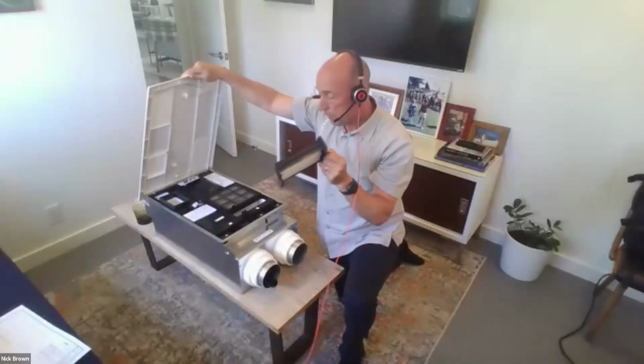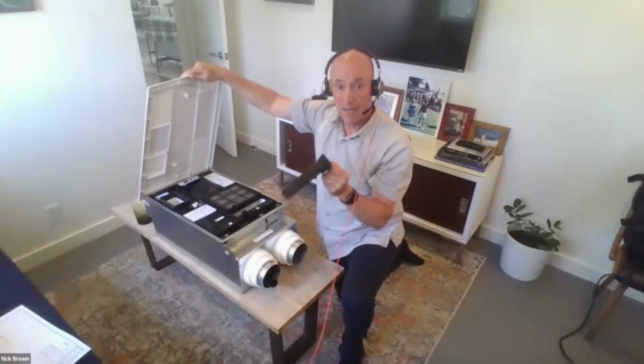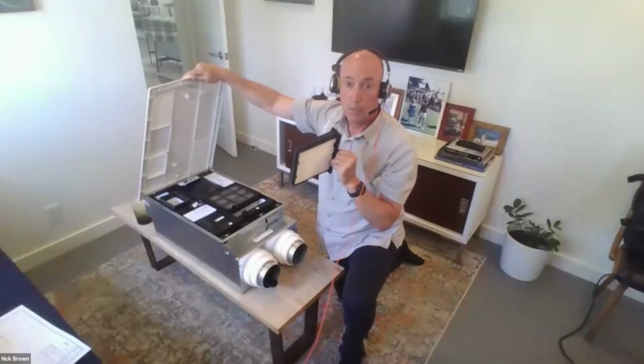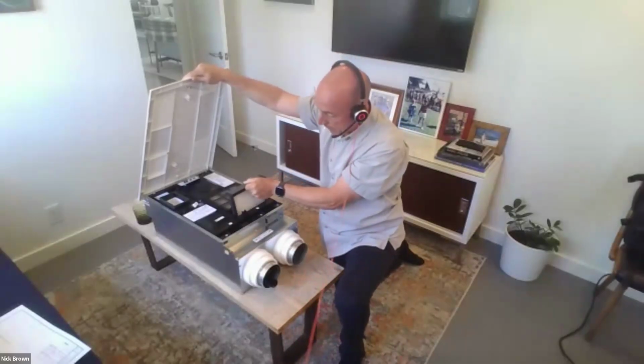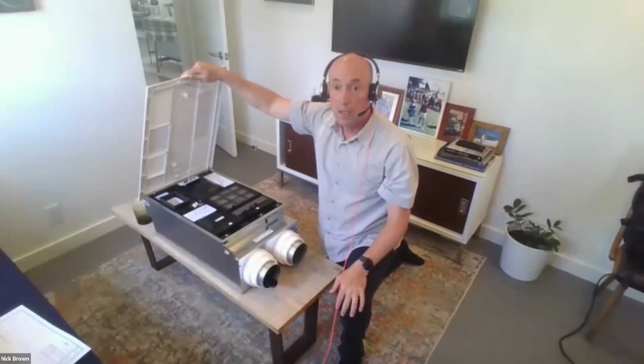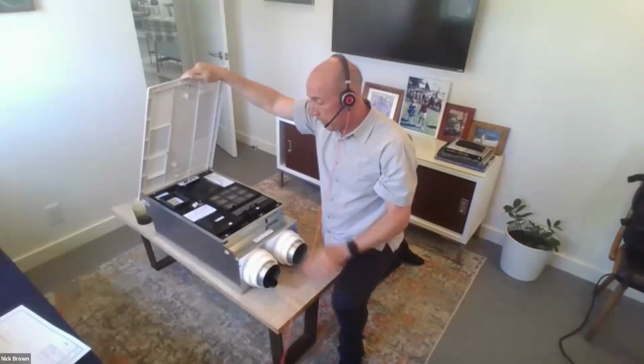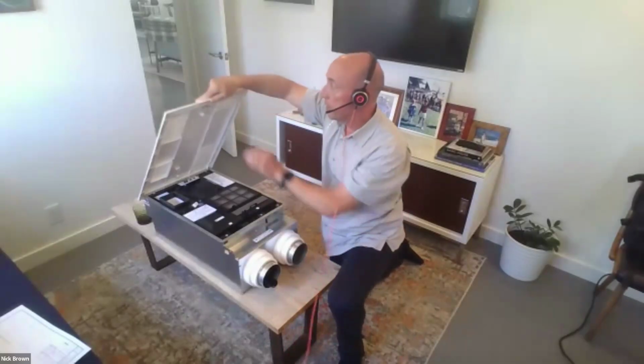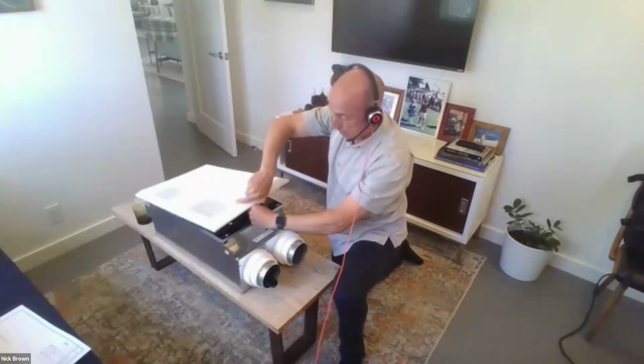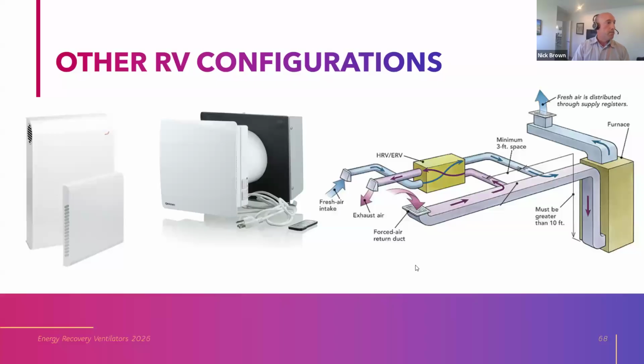I should have mentioned, in supply and balanced ventilation systems, it is mandatory to have MERV 13 filtering the supply leg of a balanced ventilation system in California. So you need to make sure you pick a system that has that capability. So I really like this adaptation because it eliminates the cost of ducting the supply and exhaust air around a small dwelling unit in a way that might allow for ERVs to be installed in multifamily buildings and small units more cost effectively. Now, I just got a few more slides.